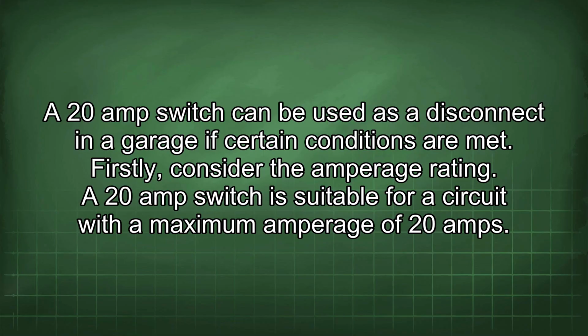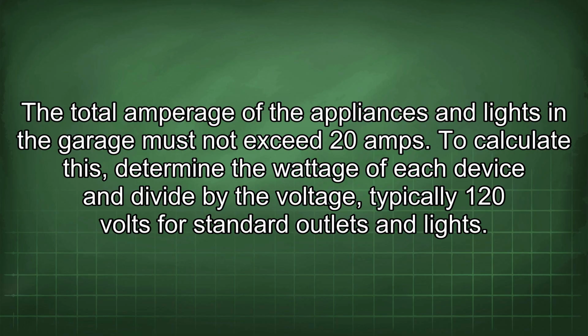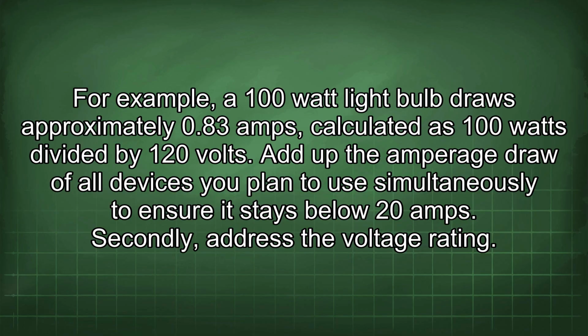A 20 amp switch can be used as a disconnect in a garage if certain conditions are met. Firstly, consider the amperage rating. A 20 amp switch is suitable for a circuit with a maximum amperage of 20 amps. The total amperage of the appliances and lights in the garage must not exceed 20 amps. To calculate this, determine the wattage of each device and divide by the voltage, typically 120 volts for standard outlets and lights. For example, a 100-watt light bulb draws approximately 0.83 amps, calculated as 100 watts divided by 120 volts. Add up the amperage draw of all devices you plan to use simultaneously to ensure it stays below 20 amps.